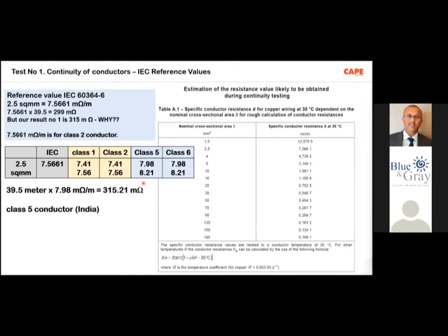Say, for example, yesterday in a webinar, 2 days back in a seminar, one of the engineers told, we have a particular motor, and always if the capacity is this much, we use 2.5 square mm wire, or let's say 4 square mm wire. Then when I asked, okay, what kind of derating factors you are applying, they said, no, we don't apply any derating factor. Manufacturer's catalog says this can handle, for example, 25 amps current, and we simply use it. Actually, we are making a mistake.